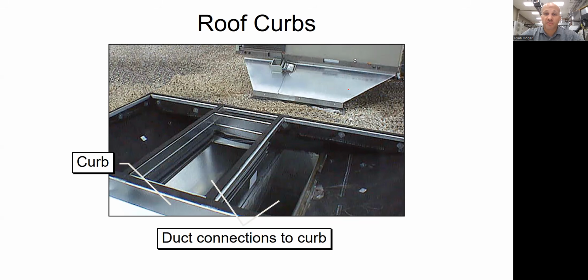If you want to change to a different piece of equipment, the ductwork connections don't always line up. In fact, they seldom line up, which means you need to take the curb out and put a new curb in, which means you've got to get the roofer involved and possibly cut the hole bigger or make it smaller, whatever you've got to do. So ideally, you'd like a new rooftop to fit where the old one fit, which means you're going to try to find one from the same manufacturer that has the same dimensional openings, or you're going to get a thing called a curb adapter, which adapts you. It's a piece you stick in between that adapts you from this curb to the new unit that you're going to buy, because it doesn't line up exactly.